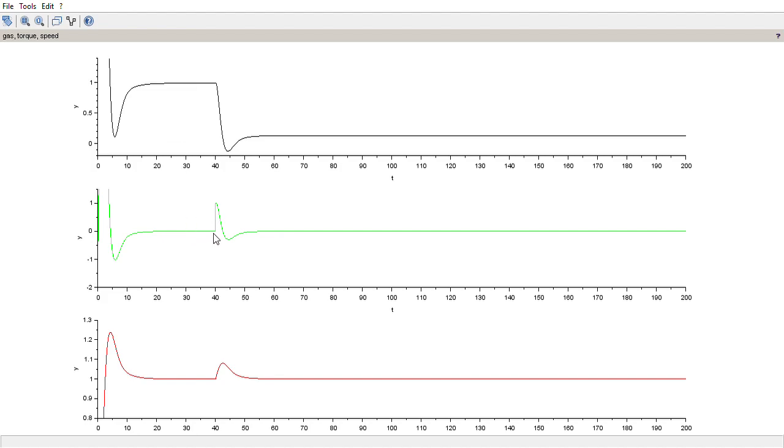So at 40 seconds, bang, I go to 1 torque, because fuel-wise, I was making enough torque for full load, wasn't I? And then I opened the breaker, so to speak, and I had excessive torque. So the governor catches it and lowers the fuel.